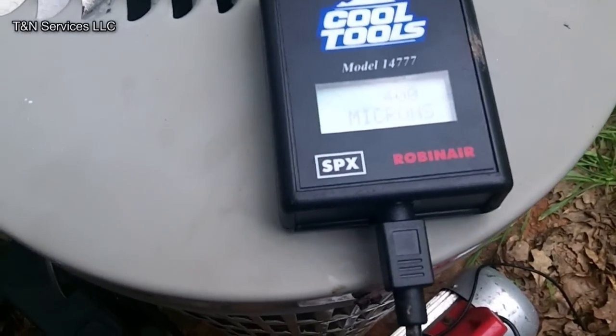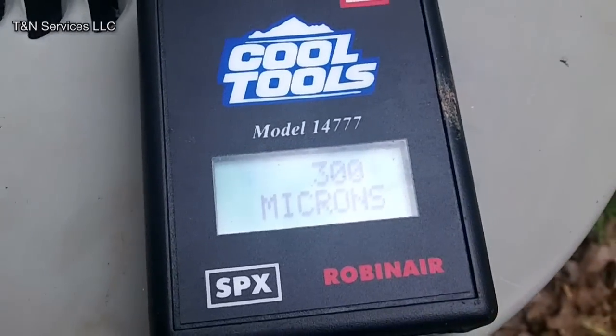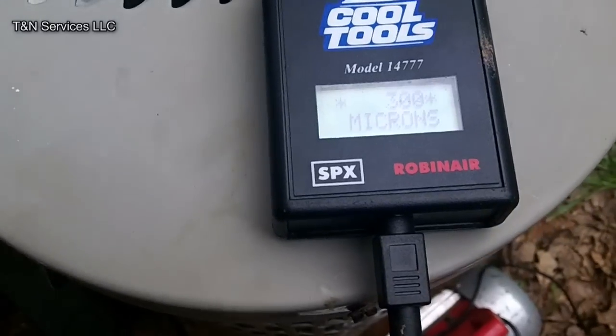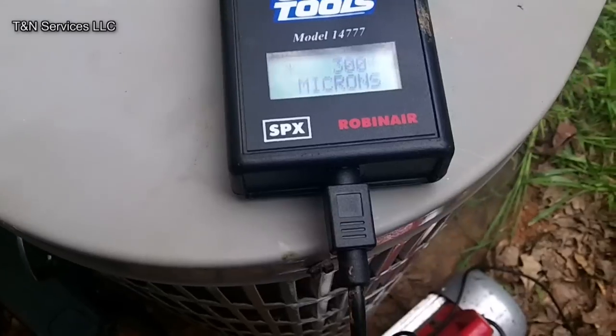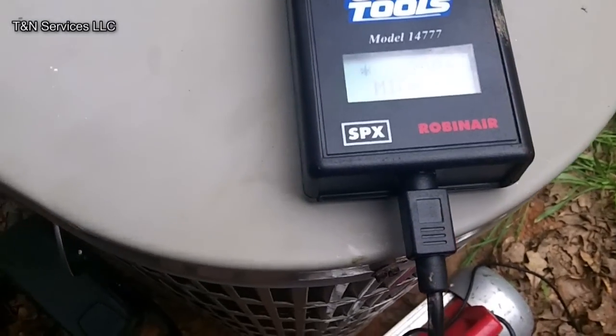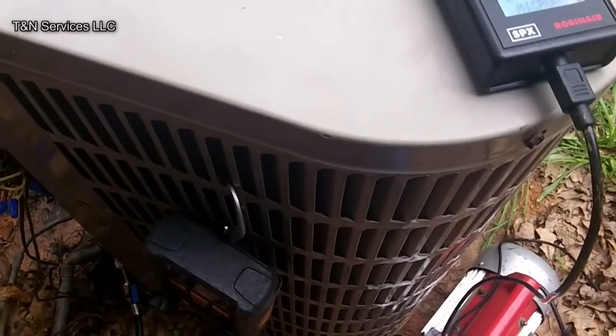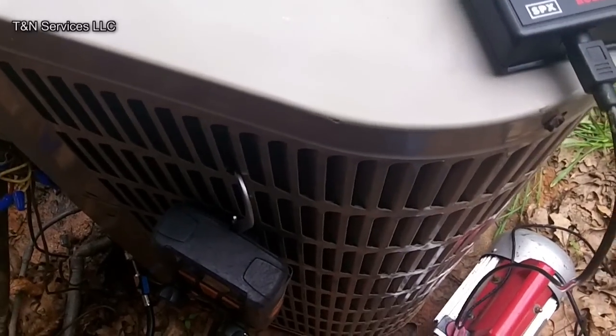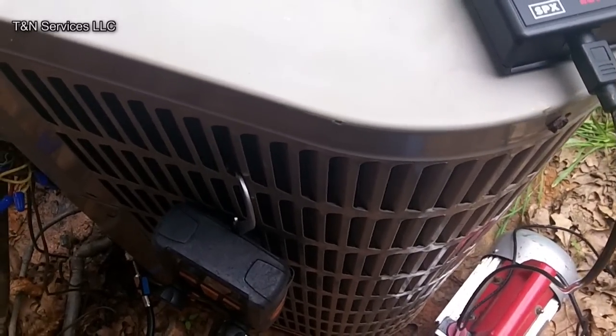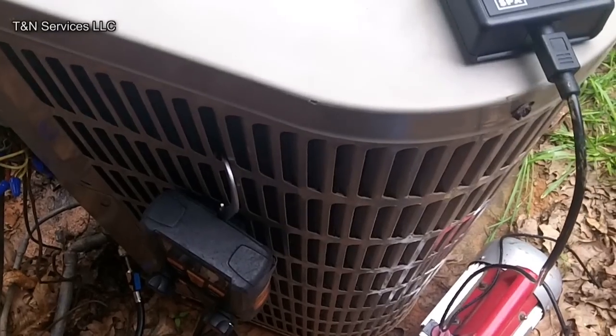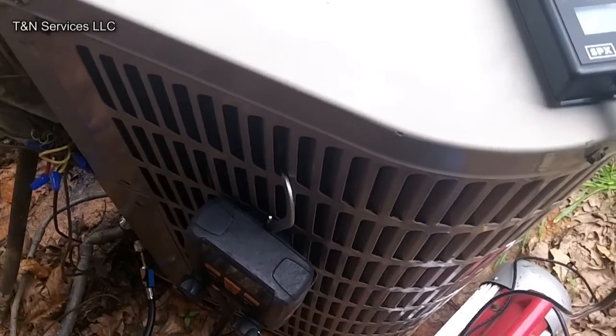We're already down to 400 microns. As you can see, 300 microns. So I'm assuming that coil doesn't have a leak on it. No wonder I couldn't find one last night. Somebody had put a lot of Freon in this thing. So of course there's no way of knowing what pressures are with that dirty coil.